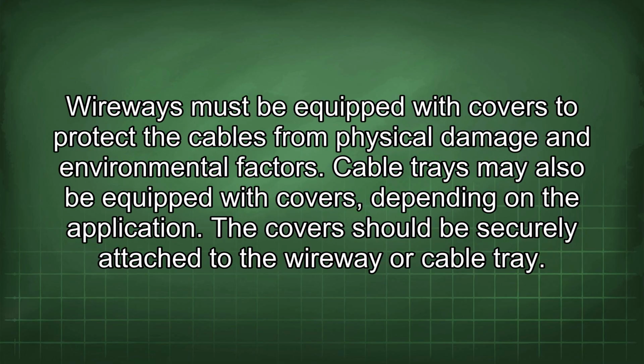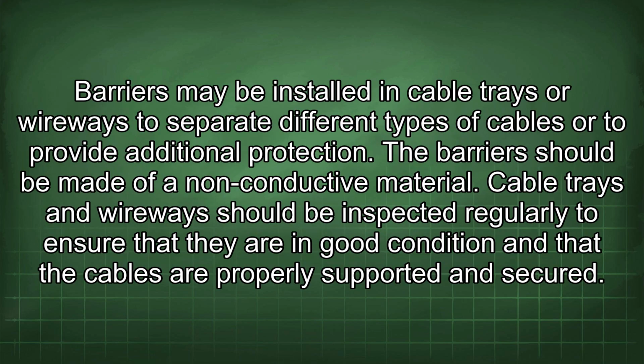Wireways must be equipped with covers to protect the cables from physical damage and environmental factors. Cable trays may also be equipped with covers, depending on the application. The covers should be securely attached to the wireway or cable tray. Barriers may be installed in cable trays or wireways to separate different types of cables or to provide additional protection. The barrier should be made of a non-conductive material.